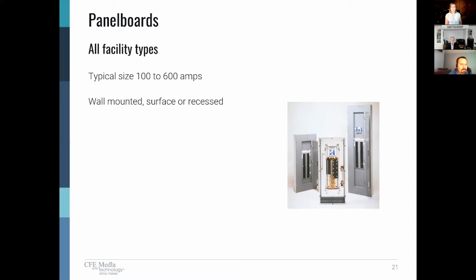Your typical panelboards, like you see there in the photo, are wall mounted. They can be surface or recessed. Sometimes you'll see those in the hallway. Very typical for lighting and receptacles. The only thing you need to know about these, in addition to the normal clearances, is there is a requirement in the code that the swing of the door be able to fit within those spaces. And it's not a problem with branch circuit panels.